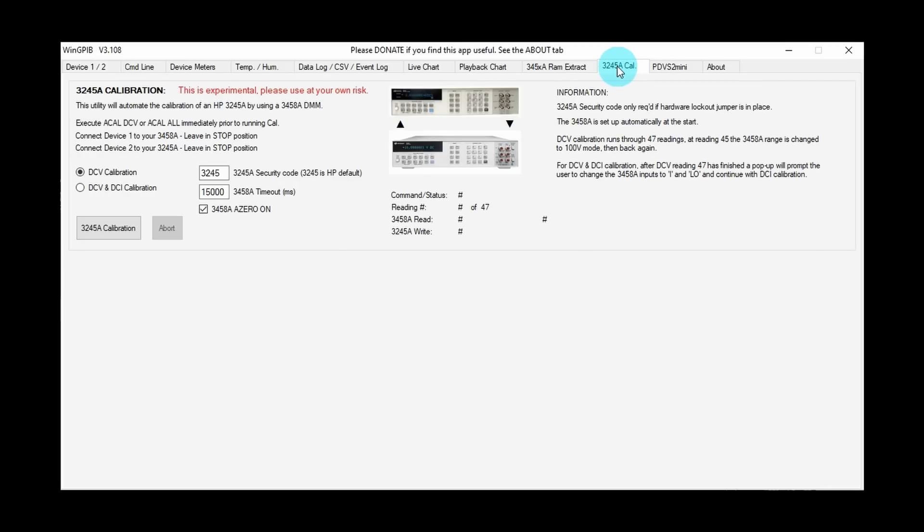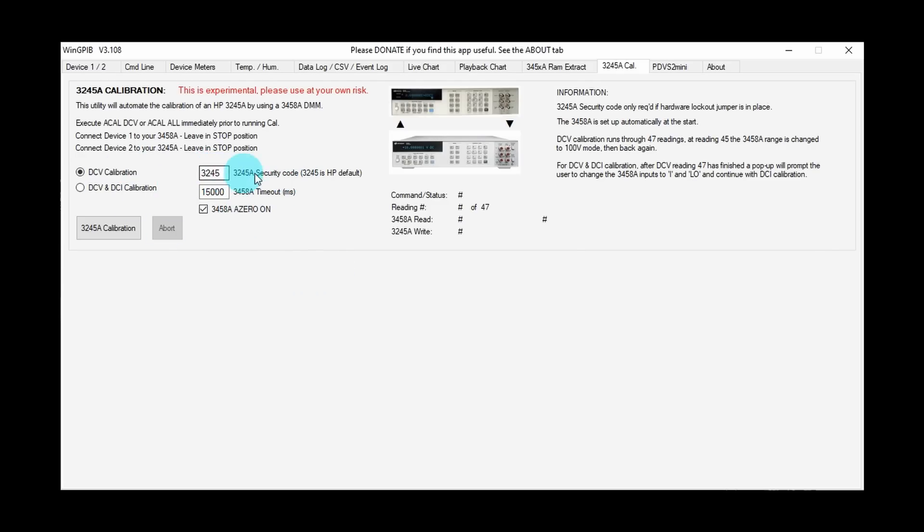And now I'll pop over onto the 3245A calibration tab. Here we are in the screen that'll allow us to automatically calibrate the 3245A using the 3458A—virtually no interaction required by the user. Just set up a few parameters here: the security code can be set here—3245 is HP default. I've verified that is the case with this particular unit. And a timeout set here—15 seconds. And I've got Azero turned on.